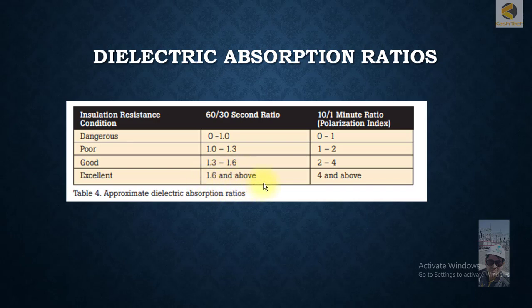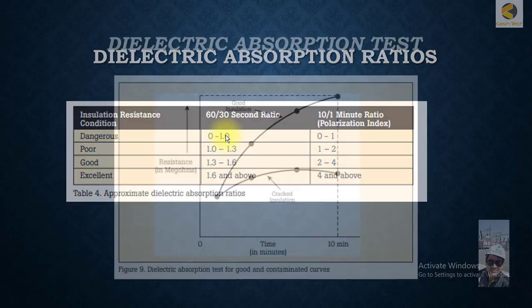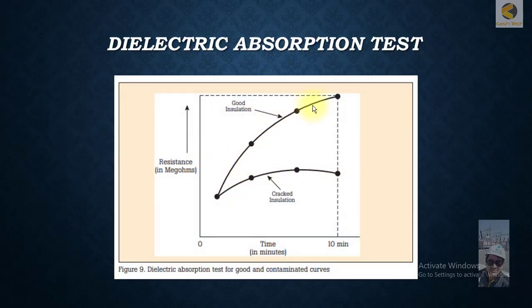This means the reading at 60 seconds is 1.6 times more than the reading at 30 seconds, meaning the resistance value is increasing, which indicates very healthy equipment condition.